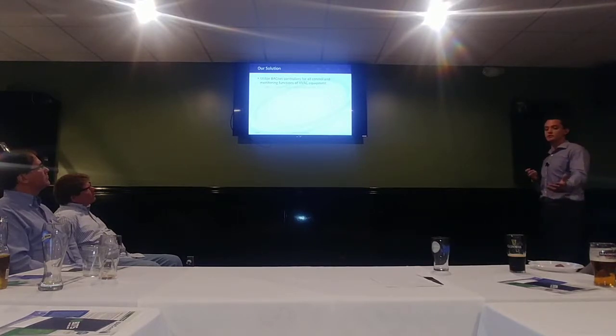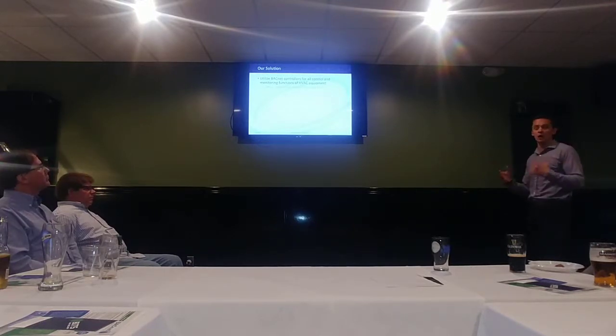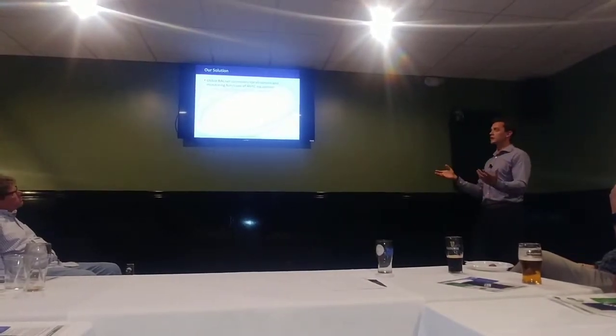Okay, so our solution. What we decided to do in this case was, option one, since we're also a Rockwell rep and Rockwell integrator, would be to put a whole Rockwell system in. So we put ControlLogix in the air handlers, you can put CompactLogix in, one processor to do 50 VAV boxes, and it's just this messy setup. It costs a lot of money, and I don't think there's a lot of value add in doing that type of topology. So what we decided to do was, why not utilize BACnet controllers for all control and monitoring functions?